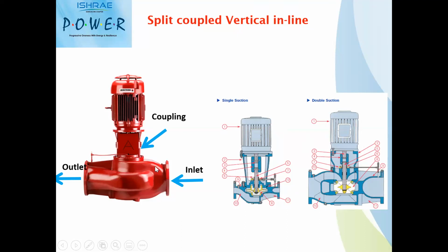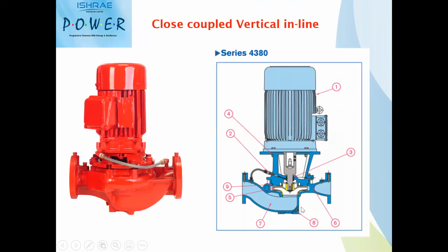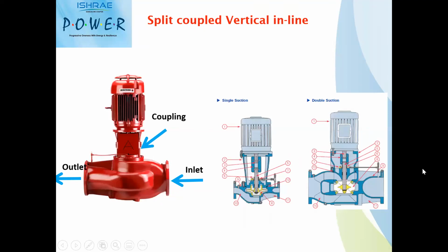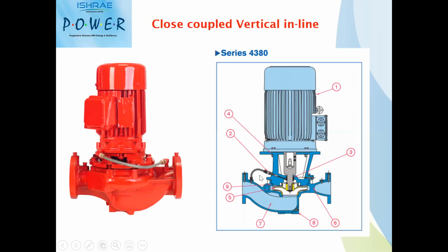This design will allow you a simple pump installation with respect to space savings as well as maintenance, which I'll be taking you through in further slides. This is a split coupled design, where you have a separate split coupling on the pump and motor shaft. This is the pump shaft, and this motor shaft is connected to a split coupling. This is a close coupled design, again in a vertical inline, where the motor shaft is extended and the impeller is mounted, very similar to the close coupled design of the end suction pump.